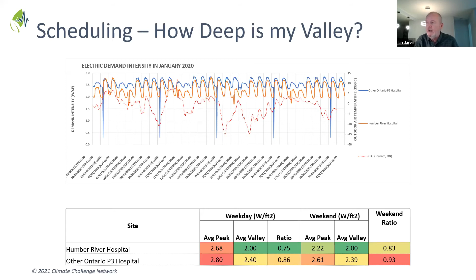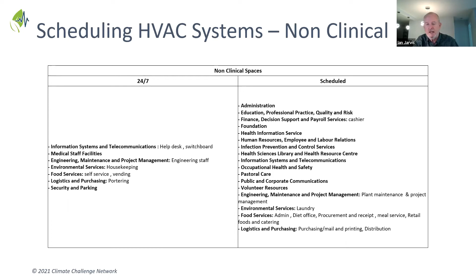So we want to dig a bit into that. This is the HVAC spaces that are currently 24/7, a very small part of the non-clinical spaces and the ones that need to be. The system design, as Bob mentioned this morning, was configured so the number of air handling units related to spaces was designed to enable scheduling. The bigger part of the non-clinical spaces is switched down at night in accordance with CSA, with fairly dramatic savings. The really fascinating part is the clinical spaces.